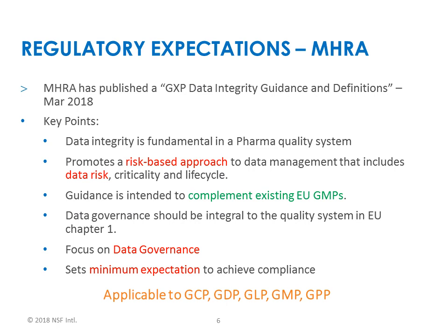To illustrate this, if we had a system that generated data and it was vulnerable to amendment, so if somebody can log into the system, generate the file, and delete the file, well, that particular system has a high data risk because the ability for that data to be amended is higher, as opposed to a system with low data risk, which would be a system where there are tight controls, and after acquisition of the data, it is protected and not available to the user to make modifications such as deleting the file or renaming the file post-acquisition.